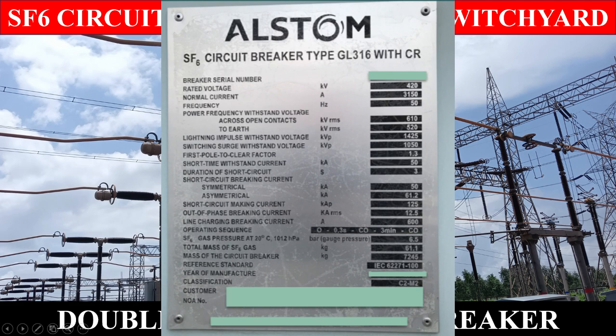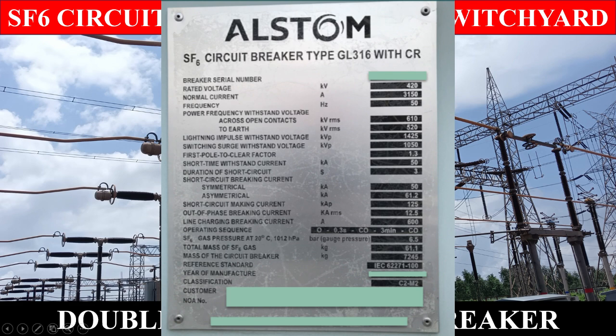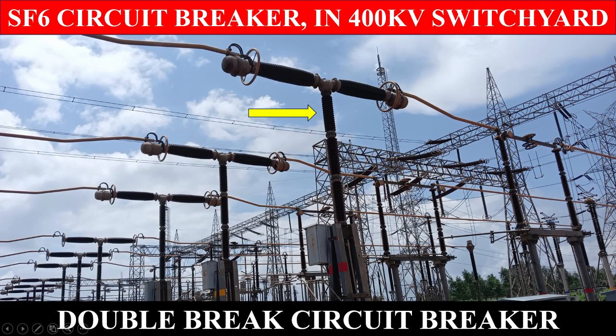Advantages. Due to the superior arc quenching properties of SF6 gas, SF6 circuit breakers have many advantages over oil or air circuit breakers. Some of them are listed below. 1. Due to the superior arc quenching property of SF6, such circuit breakers have very short arcing time. 2. Since the dielectric strength of SF6 gas is 2 to 3 times that of air, such breakers can interrupt much larger currents. 3. The SF6 circuit breaker gives noiseless operation due to its closed gas circuit and no exhaust to atmosphere, unlike the air blast circuit breaker.